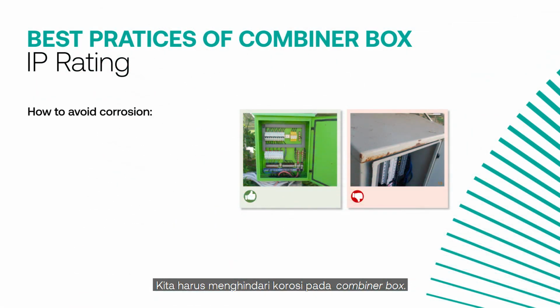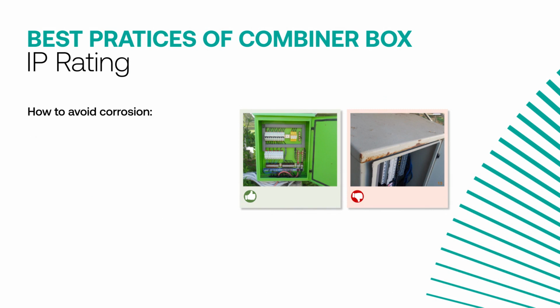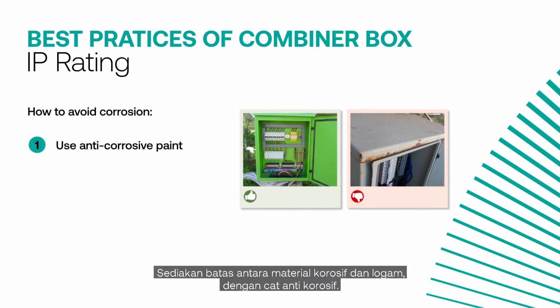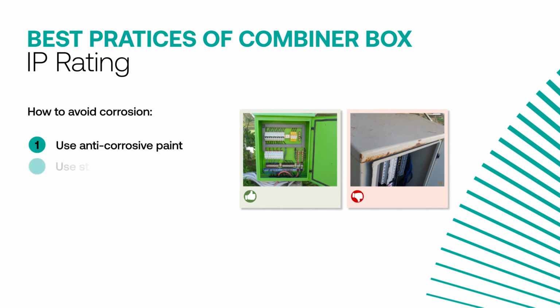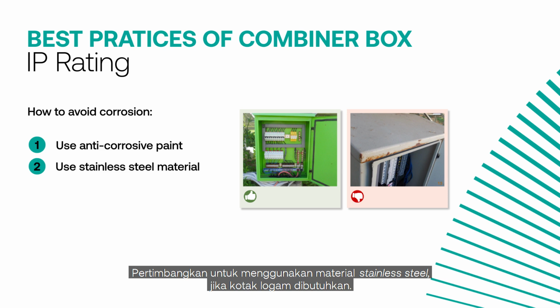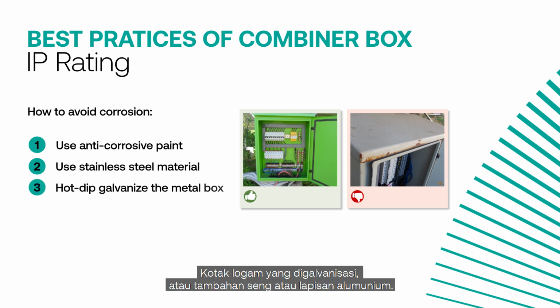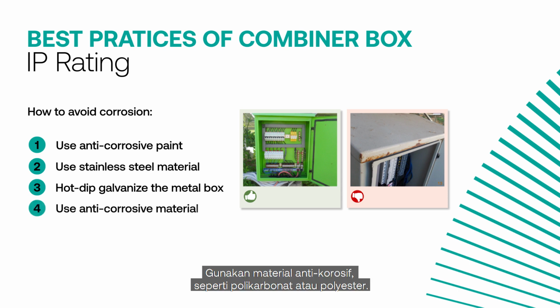We must obviously avoid corrosion in the combiner box. How? Provide a barrier between the corrosive material and the metal housing by painting anti-corrosive paint. Consider using stainless steel material if a metal box is required. Hot dip galvanize the metal box or provide an additional zinc or aluminum coating. Use anti-corrosive materials such as polycarbonate or polyester.